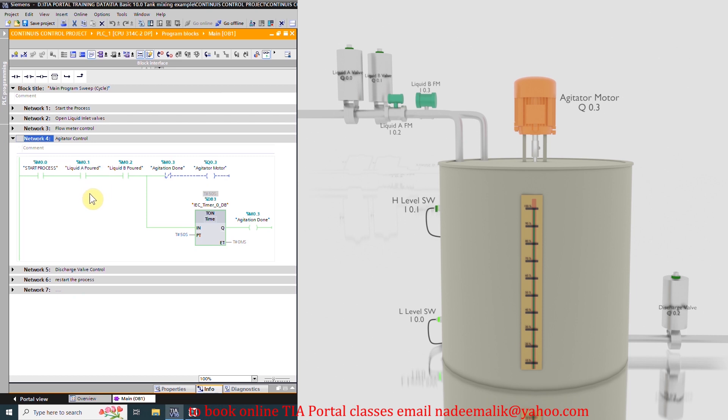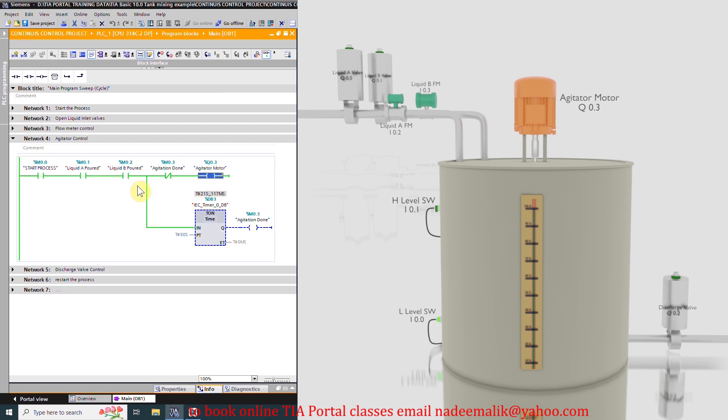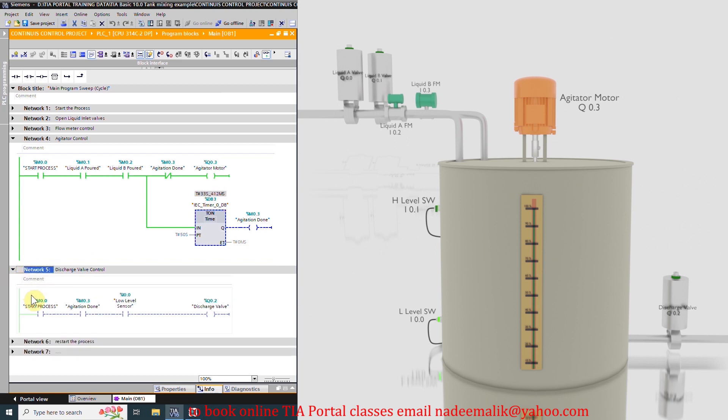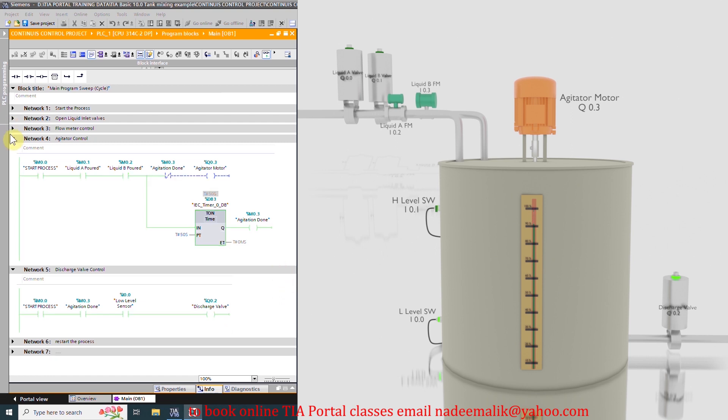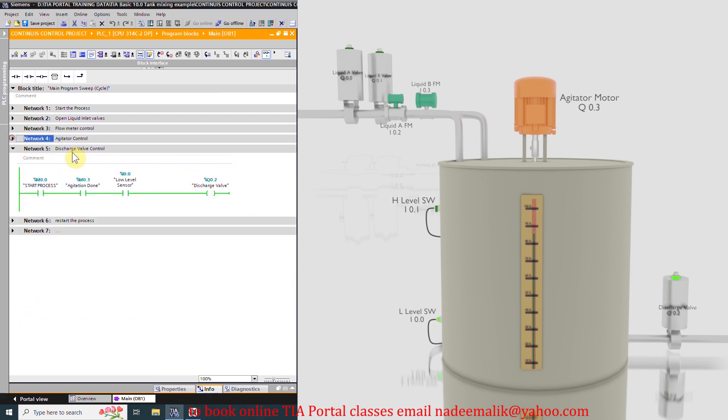As the liquid from both valves is poured into the tank, it starts the agitator motor Q0.3. As the 50 seconds are over, the timer turns on the agitation done bit M0.3, and this turns on the discharge valve Q0.2. And the tank now starts to drain or discharge.